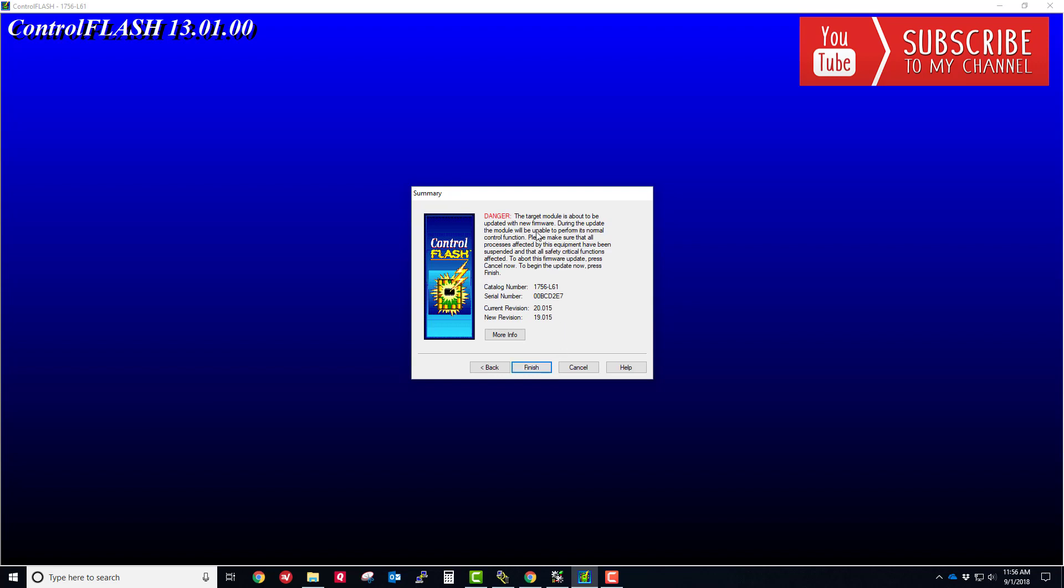You get a warning: Danger, the target module is about to be updated with new firmware. During the update, the module will be unable to perform its normal control functions. Please make sure that all processes affected by this equipment have been suspended. To abort the firmware update, press cancel. To begin the update, press finish. But we first have to put the processor into program mode. You can see the current version is 20, we're downgrading to version 19. Let's head over to the visual of the chassis itself. I'm going to flip it into program mode and then choose finish.